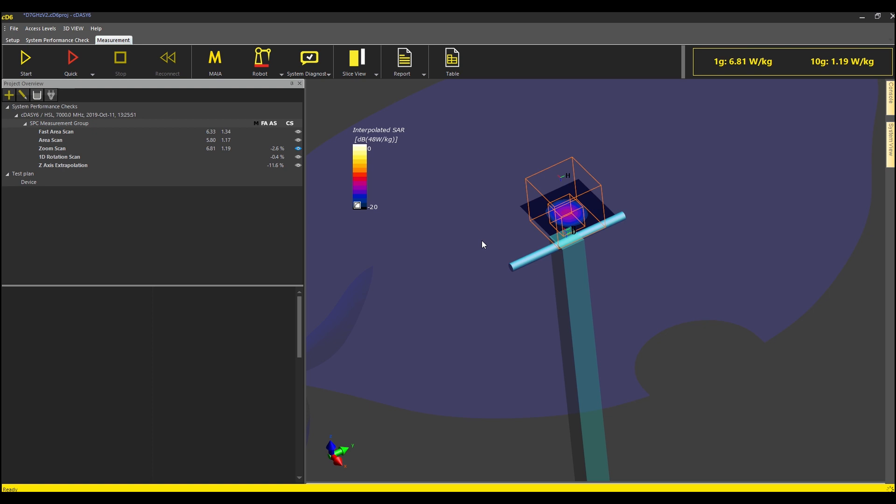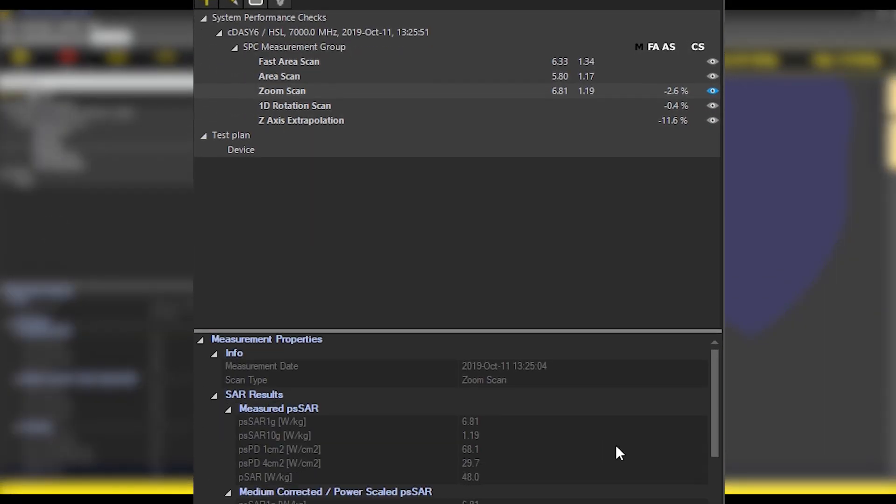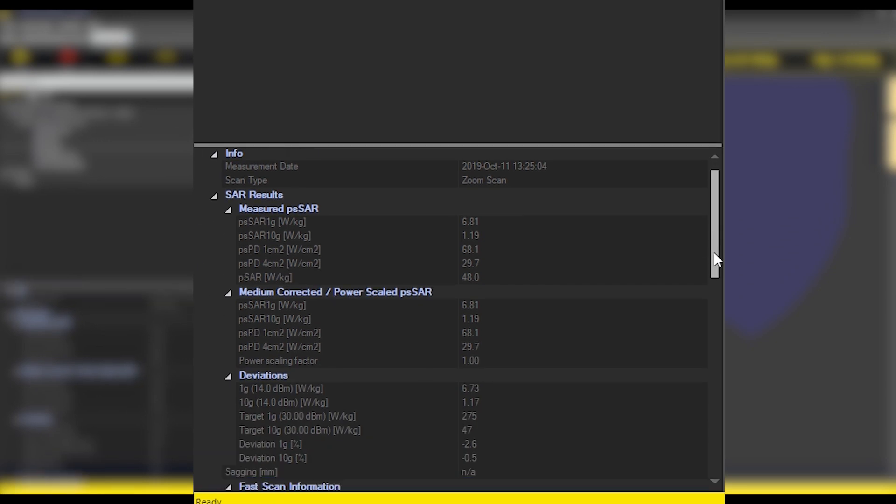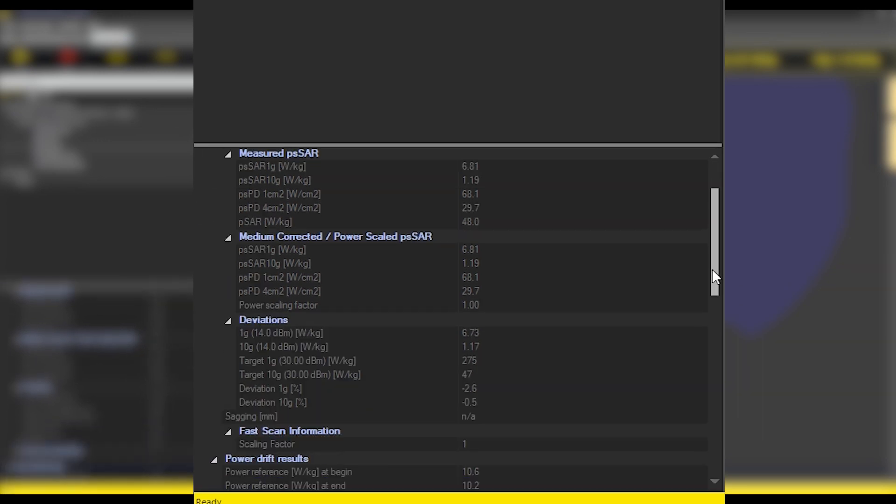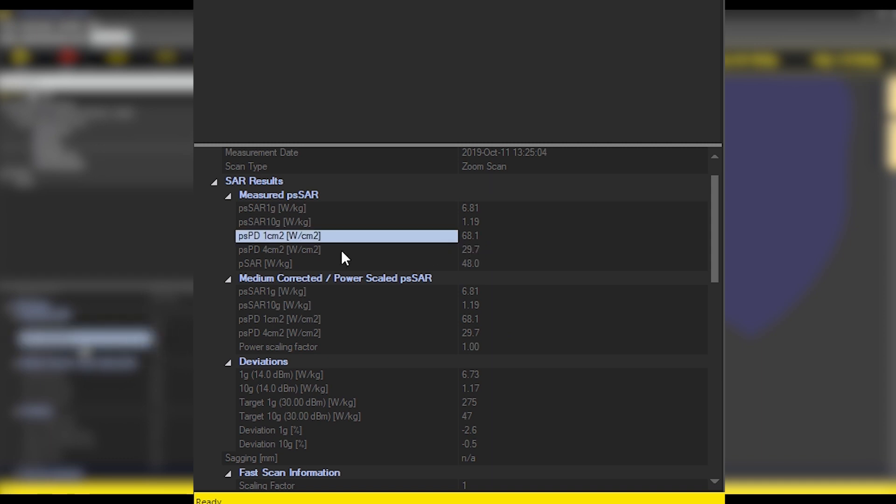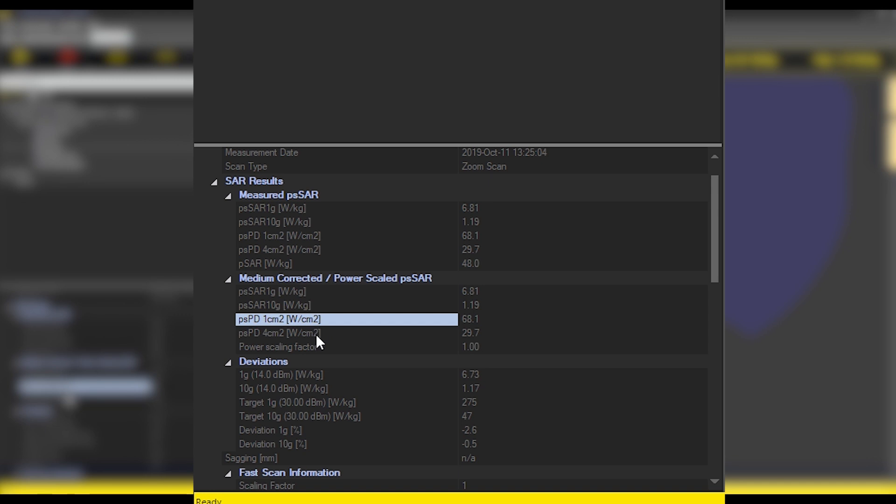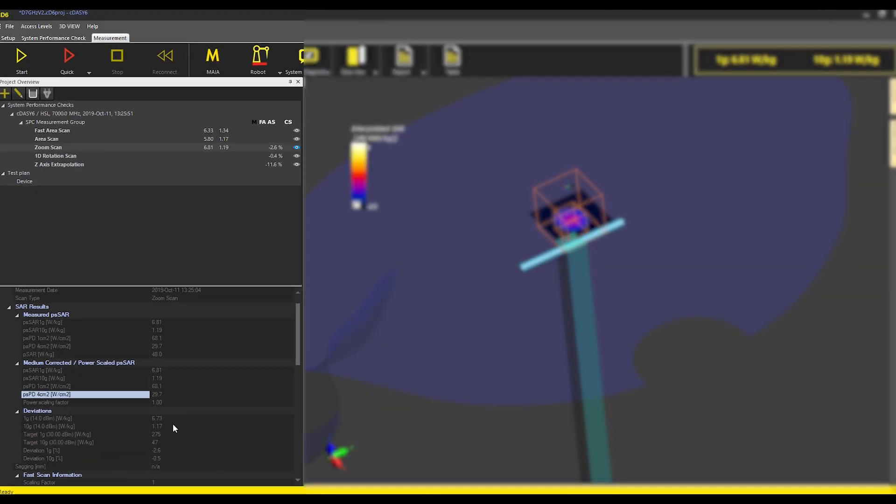To get detailed measurement results, I click on the zoom scan. The measurement properties show the transmitted power density values for 1 cm² and 4 cm² averaging area which are 68.1 Watt per m² and 29.7 Watt per m² respectively. These values compare well with the calibrated values and the deviations are less than minus 2.6%.